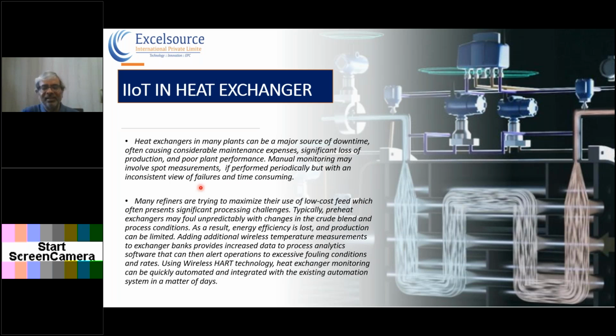We have seen that for years the heat exchanger is operated, and even though the heat exchanger has no fault inside, as an annual practice we keep using the CIP activity, and descaling is done, which uses more energy to descale. Money is also consumed. Also, a plant shutdown is required, and it generates a lot of effluent when you do the descaling activity. So by implementing IoT in heat exchanger applications, we can delay or optimize the CIP requirement.